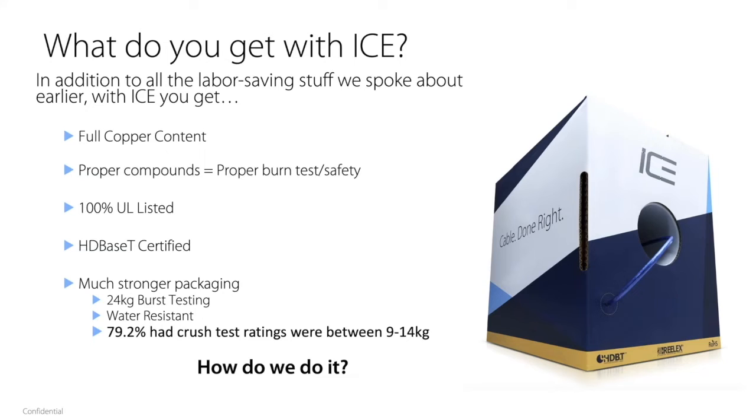Then again, matching performance to your cell phone so that your cell uses the same bandwidth as your home. And then also HDBaseT products. If you are using a Balun to do 4K, then you would want to use a Cat 6A cable because it would give you the full performance, usually a longer run length. On short runs, you could probably get away with a Cat 6, like 20 feet or something like that. But certainly as your runs get to 50 feet and longer, it's important to have a Cat 6A cable, which is 500 megahertz. Cat 6A is 500 megahertz, and a Cat 6 is only 250 megahertz. So you're getting double.